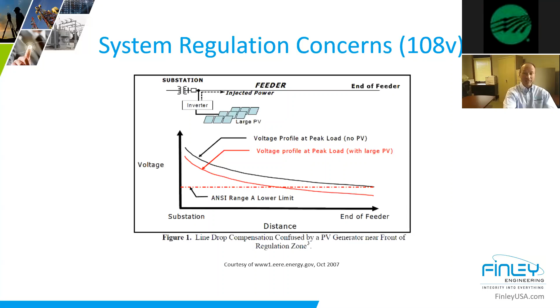Maybe you've got midstream regulation, whatever. But let's say in this model, we've got substation regulation. And if you see the black curve there, we've got a typical profile. You've ramped it up to something high enough at the sub that at the tail end, you're still meeting standards, and you're fine. But with an injected source close to the substation, you have the potential for, and read my figure there, you've got the note, line drop compensation can get confused with that depending on how they're set, where that regulator may not step because of the injected source, but you could end up with tail regulation concerns. I think that's an interesting one. People may not realize that's happening if you're not out there reading that.